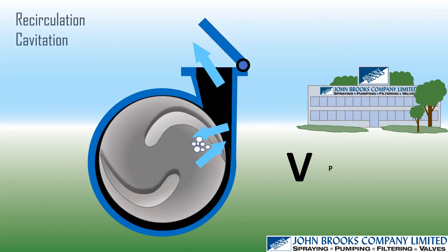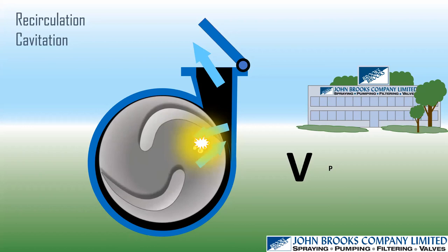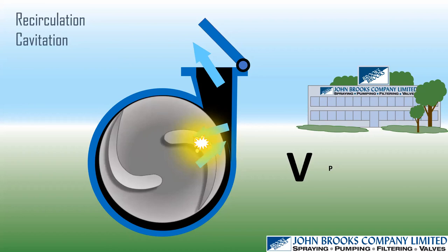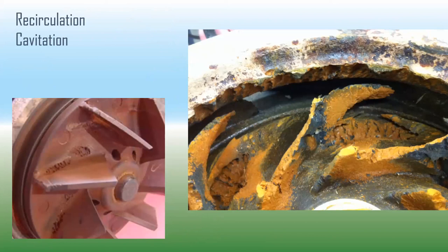This is the hardest thing to imagine: dropping the pressure so much on the discharge side of the pump that vaporization occurs. Recirculation cavitation is not very noisy and usually affects the midsection of the impeller vane — whereas suction cavitation affected the center or leading edge. Discharge cavitation takes this to the limit — what happens when we perform the shutoff test, with the valve completely closed. This recirculation definitely occurs, and there's not enough area across the front face for all that fluid to recirculate. The fluid finds the gap between the pump casing cutwater and the impeller vane tip to slip back to suction.